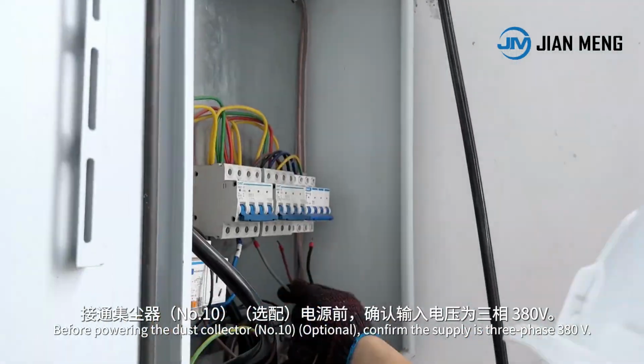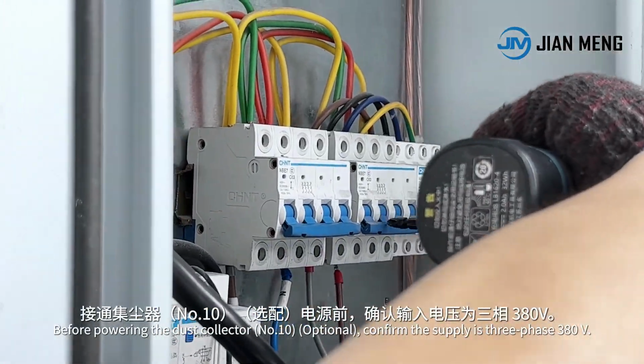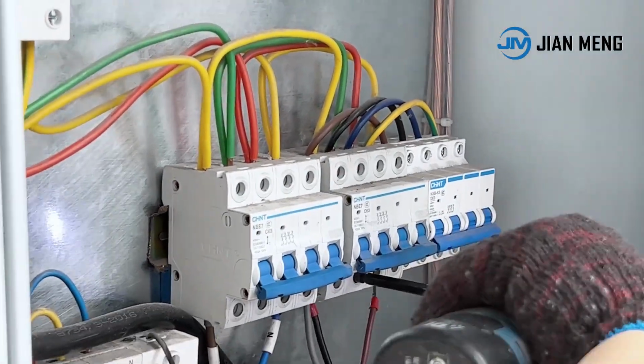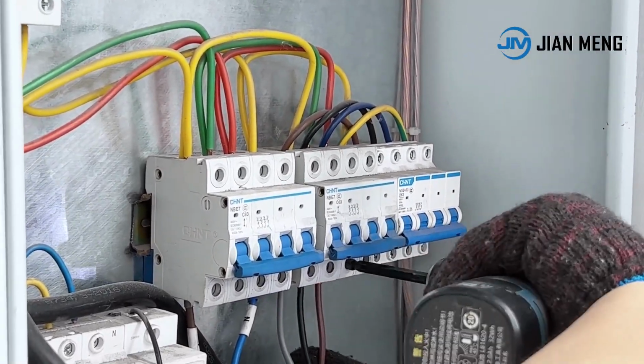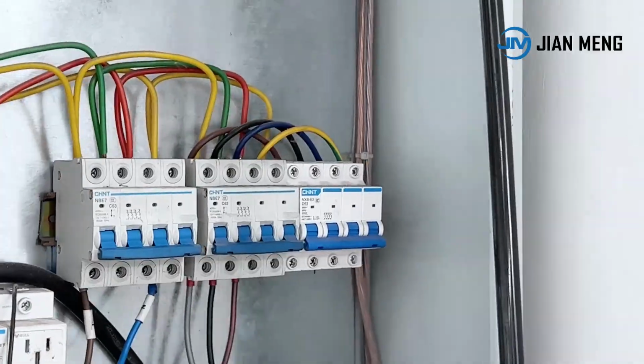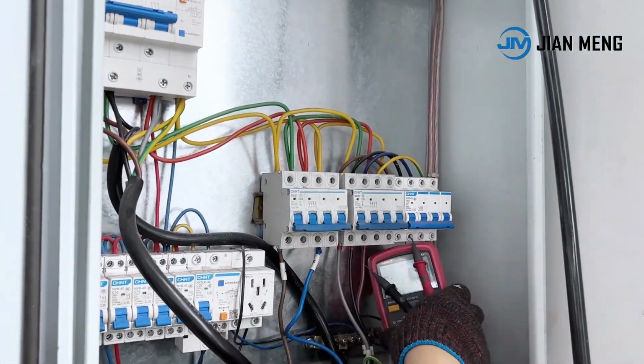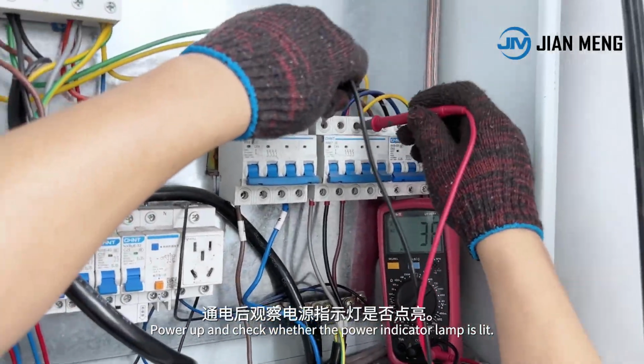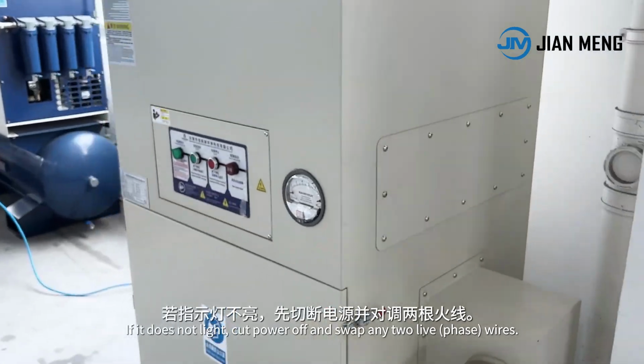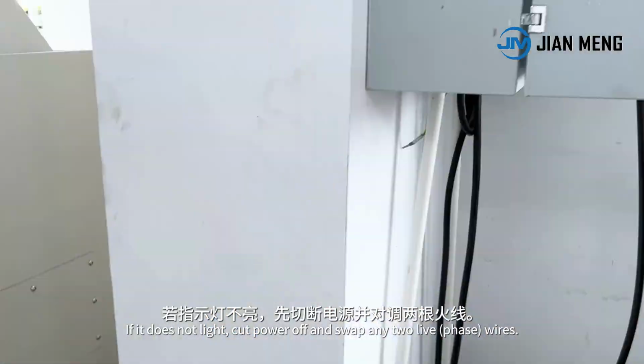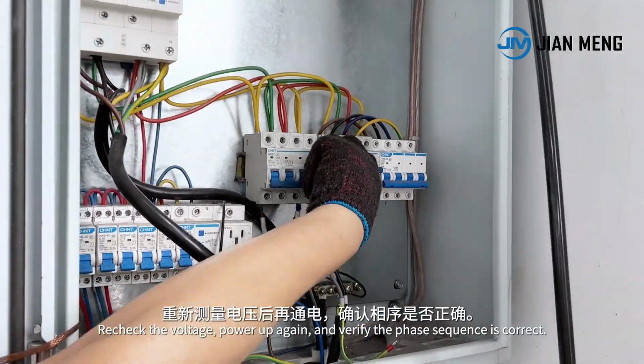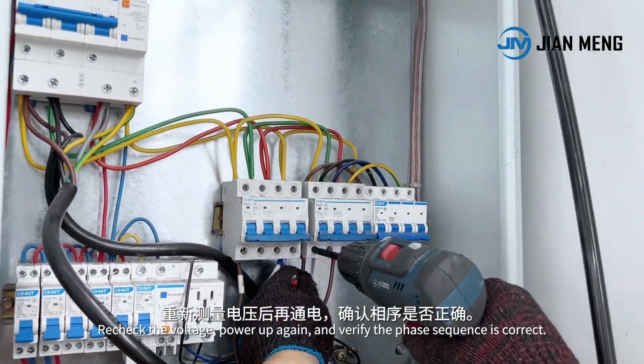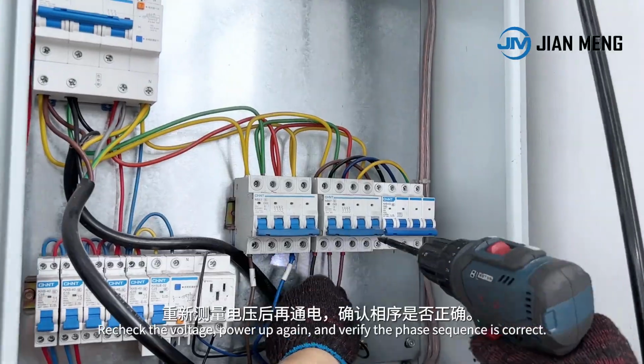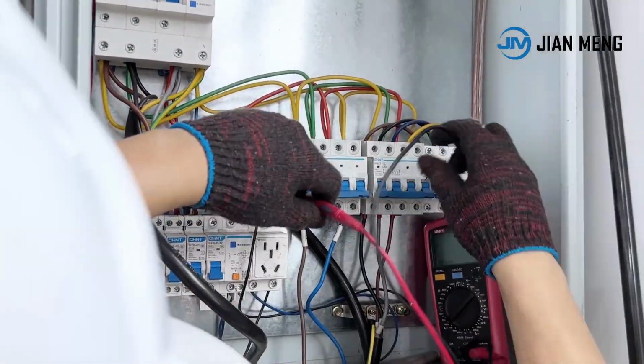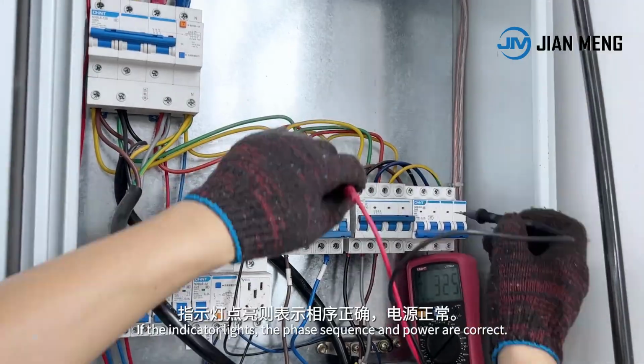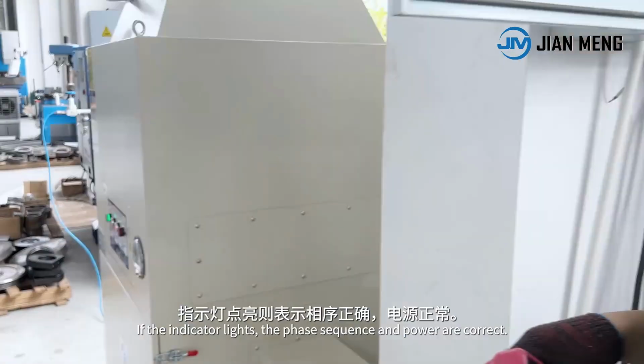Before powering the dust collector number 10, optional, confirm the supply is 3-phase 380 volts. Power up and check whether the power indicator lamp is lit. If it does not light, cut power off and swap any two live phase wires. Recheck the voltage, power up again, and verify the phase sequence is correct. If the indicator lights, the phase sequence and power are correct.